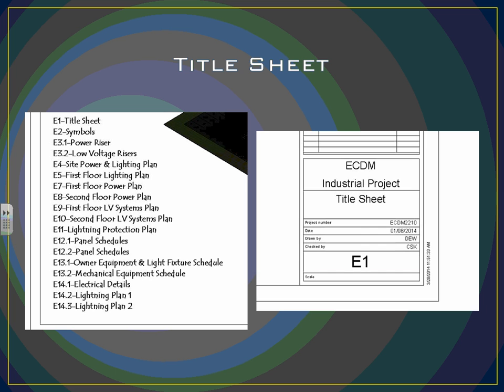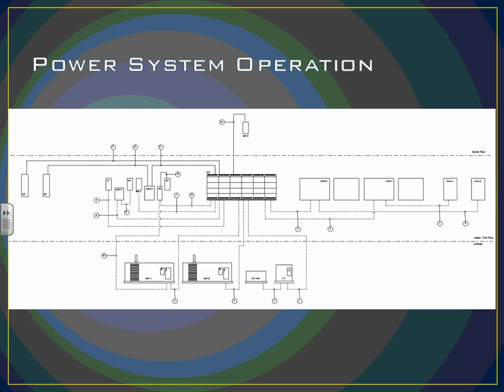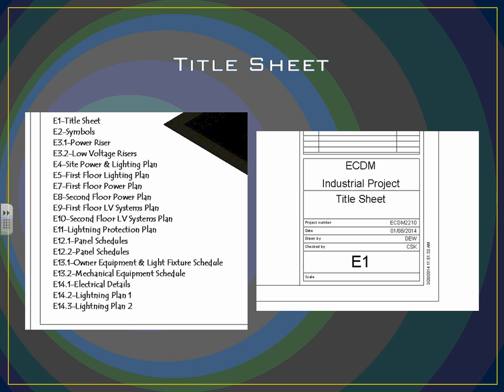So service for our building is 480/277. It's a 3-phase 4-wire. Main service entrance equipment is a UL 1558 switchgear. And like we said, we set it up for calculation for a 15% growth for our generator and switchgear. Just briefly for emergency power in general, we did life safety for egress lighting, exit lighting, and 100% of the building electrical power. And then our switchgear will be parallel equipment used for a closed transition for ATS and switchgear. And then I guess here we get the power system.